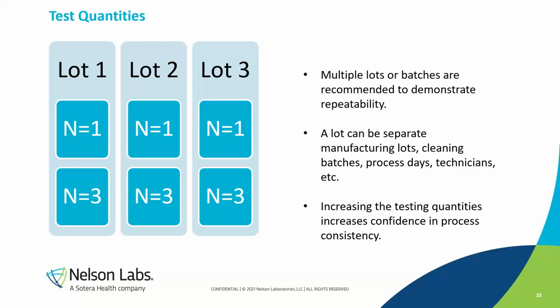Sometimes that's just 3 lots of 3 for a total of 9 data points. Again, in the statistics world, that's not a huge difference, but it's sort of theoretical versus reality. And with reality, you're doing the best you can. Randomly, I saw pushback where 15 was encouraged. There wasn't really a reason given behind that, but it happened. So if you have a higher risk device or you want just a little more confidence, you might increase that number from 3 lots of 1 up to whatever is reasonable.